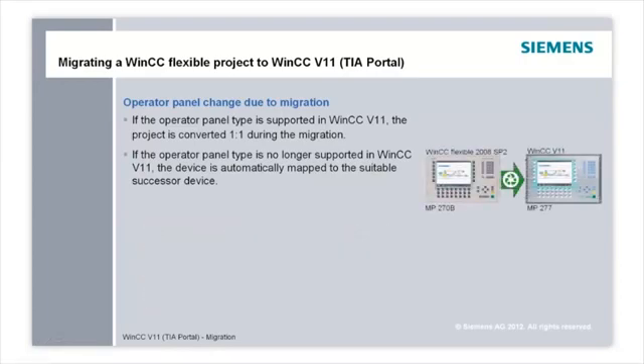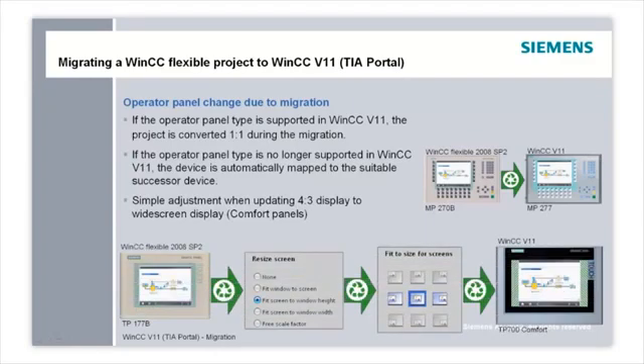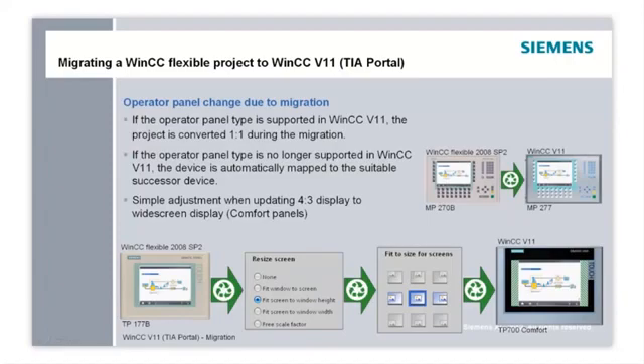WinCC version 11 also supports you regarding settings such as screen resolution, and arrangement and size of elements on the display. You can, for example, specify prior to the migration how to place the contents of the migrated pictures on the new operator panel. This is a particular advantage in the case of widescreen resolution on the new operator panel. In the displayed example, the TP177B with a 4:3 resolution is migrated to a TP700 Comfort panel with widescreen resolution, with the configured picture adopted using the preset Fit Screen to Window Height option.